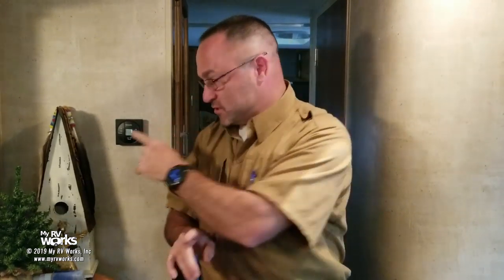Now furnace. With this thermostat you cannot have the air conditioner and the furnace on at the same time. But you can have the blower motor on and the furnace on at the same time — there may be benefits to that. Heat rises from the floor, you have your fan on because you've gone to door number one and locked it into low or high fan. Then you go to door number three, which is furnace, turn it on, set your set point. As long as you leave your fan on low or high, it will run constantly — it doesn't care what the temperature is. That fan will stay running on low or high regardless of temperature, because you told it to.